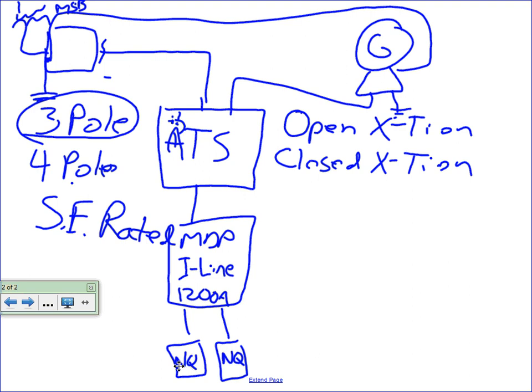This equipment also, the big difference is, it has to withstand the fault current for 30 cycles, or half a second. So if you have 100,000 amps of fault current available, it's got to be able to take that 100,000 amps for at least half a second before it goes offline. Switchboards are what we call AIC rated, amps interrupting capability. They may be able to take that 65K, but the breaker's going to take that fault off within a couple cycles.